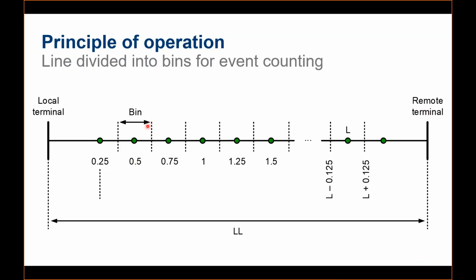at all times. Whenever you have faults, a disturbance, or low energy events, there is a counter. It will keep counting and incrementing that counter to predict if there is any incipient fault in that location. So once the counter counts up to the value, for example, you set 5 events in 24 hours, once that counter reaches 5, it will give you an alarm. So you can send your crew to that particular location for inspection and preventive maintenance.